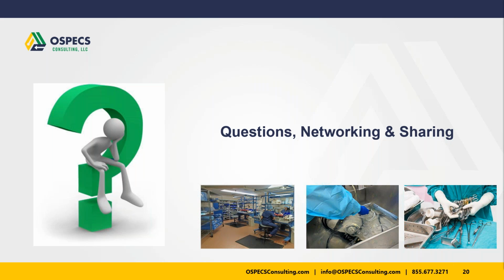Okay. We've got a couple other questions. One of them is, what are the acceptable levels of steam quality parameters per AAMI ST79? I will be happy. It's one of my favorite questions. So steam dryness, which is a measure of the water vapor content in the steam, should be at least 0.97. What does 0.97 mean? It means that it's 97% water vapor at least, and 3% water, but where? Well, ST79 isn't so clear on that. The answer to that question is that it's on the steam coming to the sterilizer.